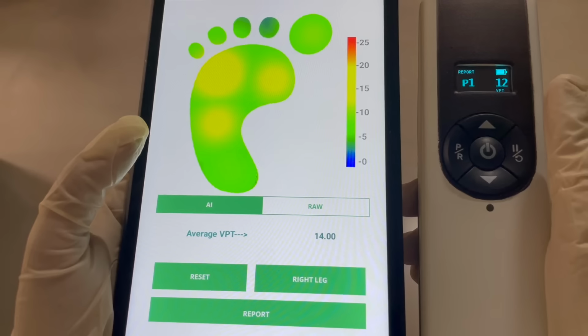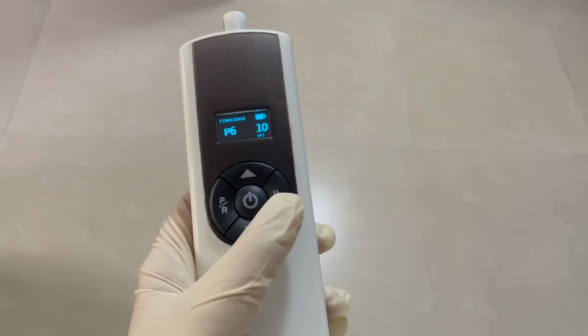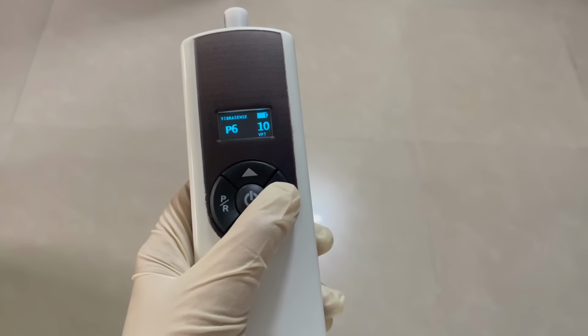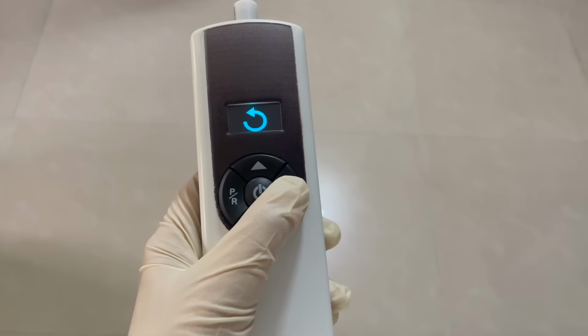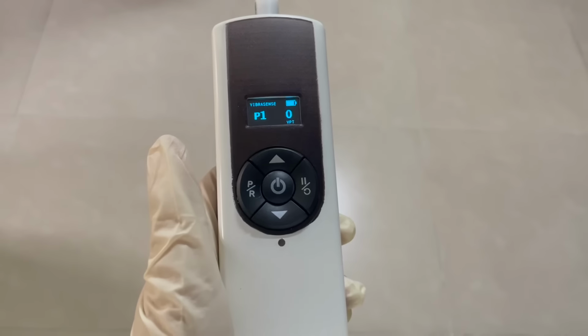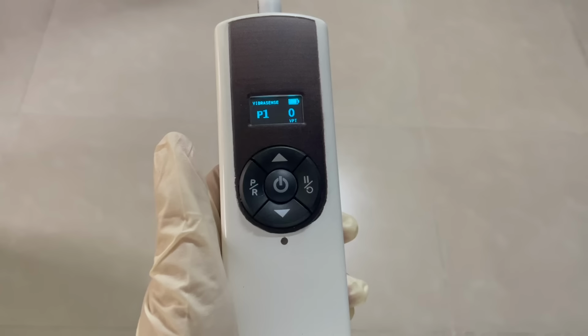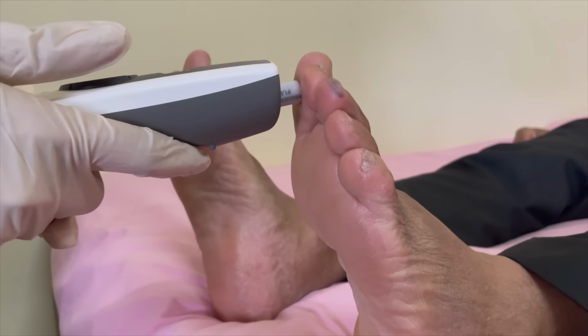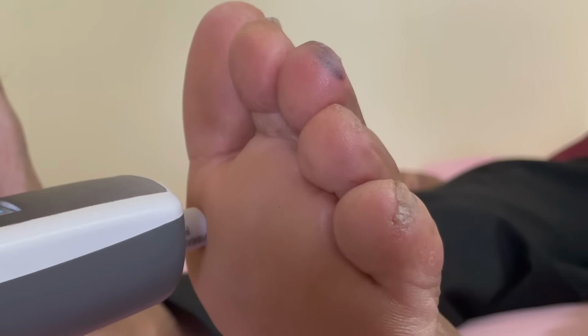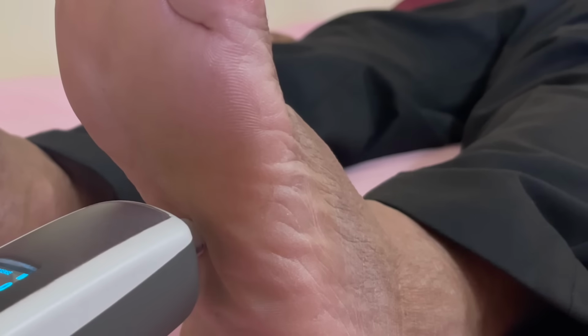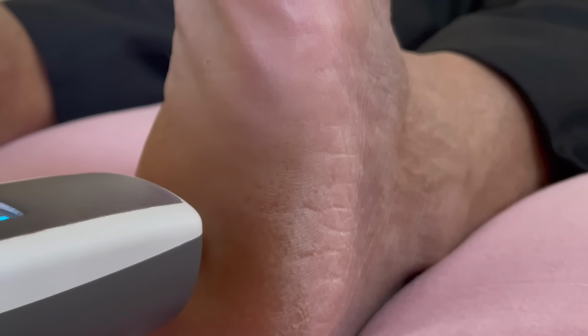Before you proceed to test the other foot, you need to reset the device by pressing the PR button once and then pressing the reset button for about 3 seconds. This will bring the device back to P1 and VPT to 0. Now proceed to test the other foot following the same steps of testing from P1 to P6.